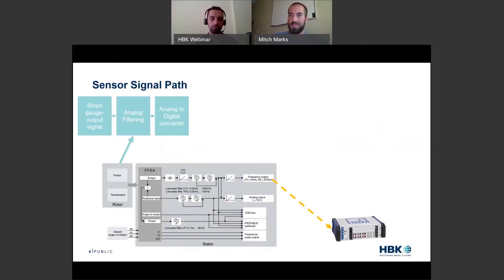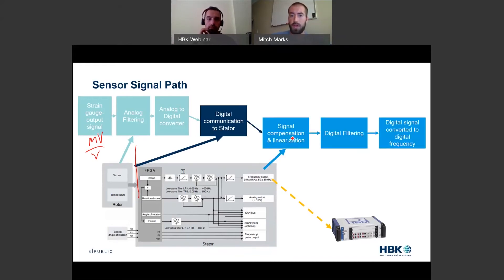So if we follow the signal path - and I made this slide for a customer a couple months ago and kind of liked it - on the rotor we have this void between rotor and stator. We have strain gauge output signal, the millivolt per volt signal. We have some analog filtering, analog digital conversion, and then we pass that through an air gap. Digital communication, actually at a high frequency, to the stator.